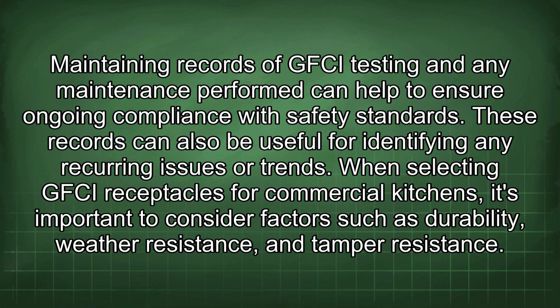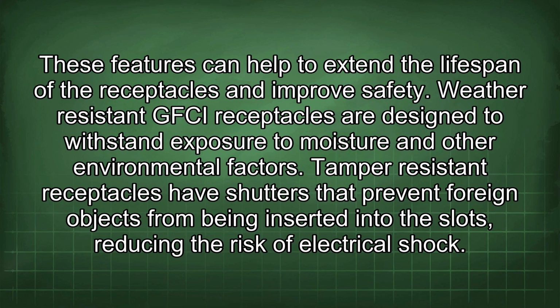When selecting GFCI receptacles for commercial kitchens, it's important to consider factors such as durability, weather resistance, and tamper resistance. These features can help to extend the lifespan of the receptacles and improve safety. Weather-resistant GFCI receptacles are designed to withstand exposure to moisture and other environmental factors. Tamper-resistant receptacles have shutters that prevent foreign objects from being inserted into the slots, reducing the risk of electrical shock.